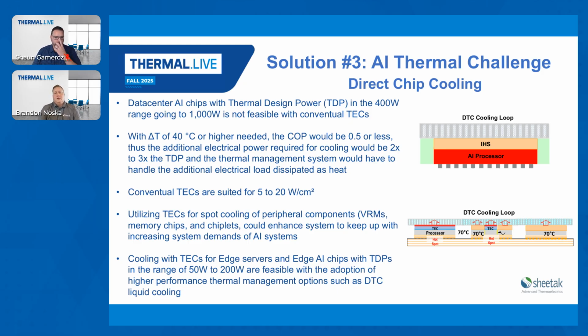Now, looking at direct chip cooling, the TDPs that Sean mentioned, 400 watts going up to 1,000 watts, that's really not feasible for a single TEC module to manage. The heat density is too high, and with this coefficient of performance, if you're trying to drive 30 or 40 degrees temperature difference directly at the chip with the Peltier cooler, the COPs will be below 1, and you'll be dissipating more heat than what you're cooling, at a factor of 2 to 3x. Your power requirements for the system go up. So we're not really arguing for direct to chip cooling for these high TDP AI chips—the COP and the heat density just aren't there at this point. Conventional TECs are more suited for 5, 15, 20 watts per centimeter squared at an individual chip level.